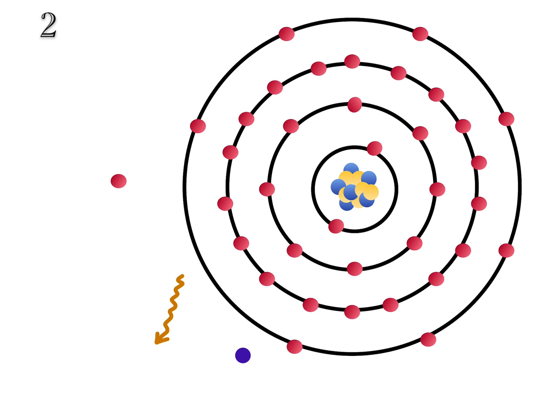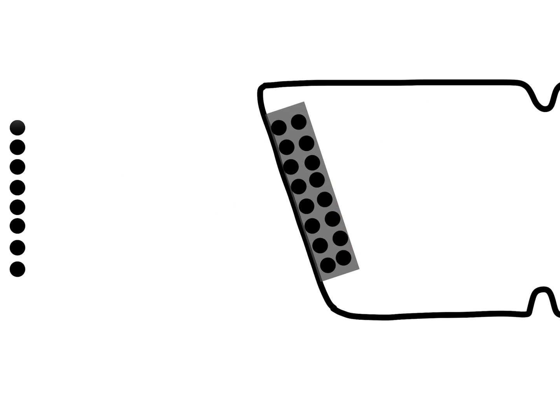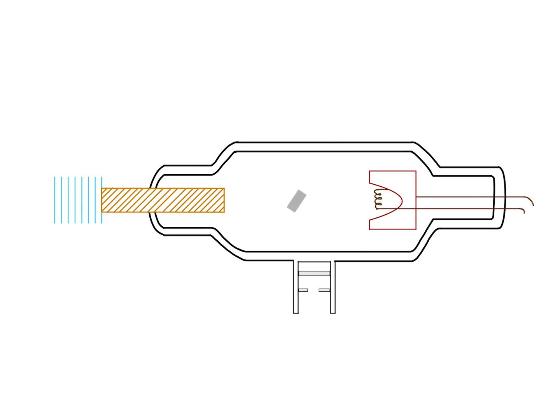These heat-based interactions are quite common because each and every specific bombarding electron interacts with outer shell tungsten electrons as a whole producing a significant amount of heat at the target. That's the reason the tungsten target is embedded in copper block to prevent damage from the heat.